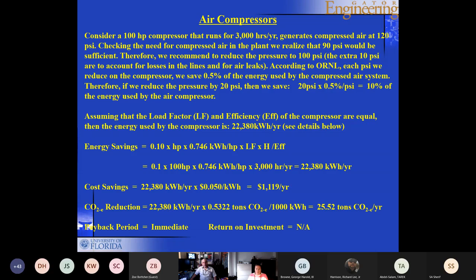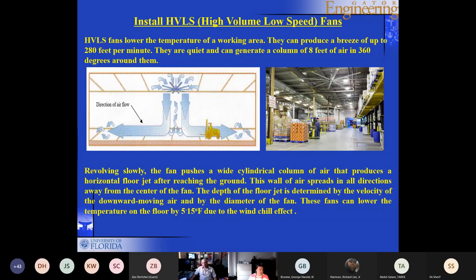You multiply it by 100 horsepower, convert it into kilowatt hour, the multiplier 0.746, by 3,000 hours per year, you end up with 22,380 kilowatt hour per year of savings. Your cost, that would be that number multiplied by 5 cents per kilowatt hour, $1,119. The CO2 reduction would be multiplying it by 0.5322, dividing by 1,000, you get 25.5 tons of CO2 per year. And the payback here is actually immediate, because you really haven't done anything. You haven't purchased anything. So therefore, you haven't invested any money in it. It's a low-hanging fruit. The payback period is immediate, and the return on investment does not apply in this case. Doesn't have any physical meaning, because you haven't invested anything.